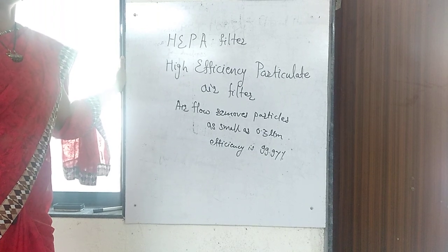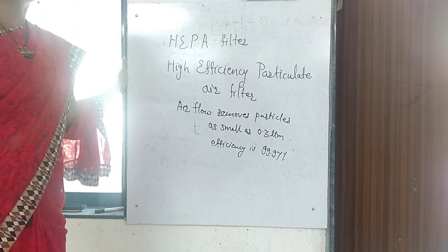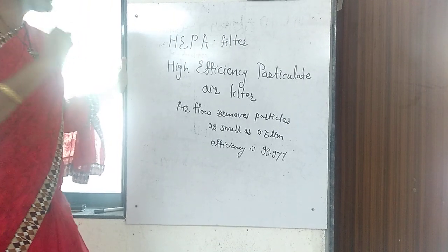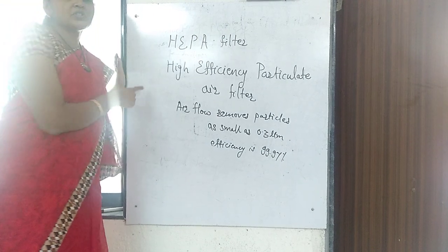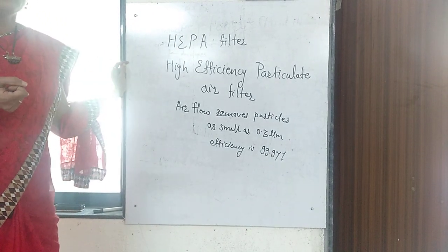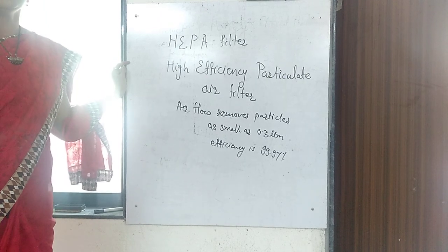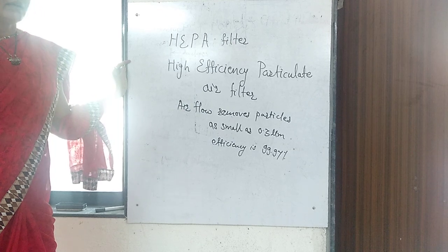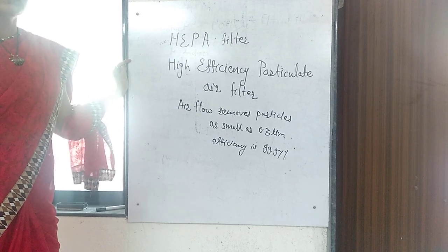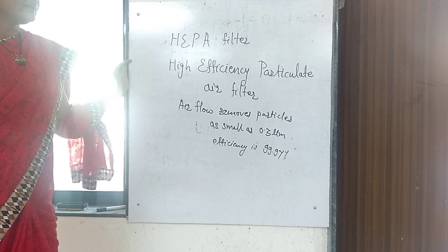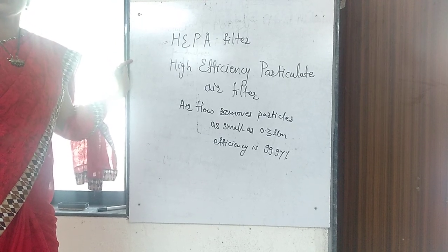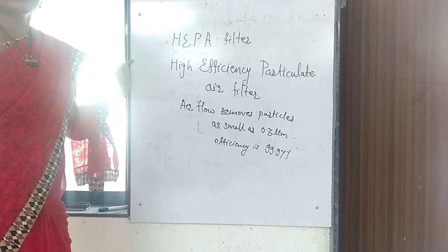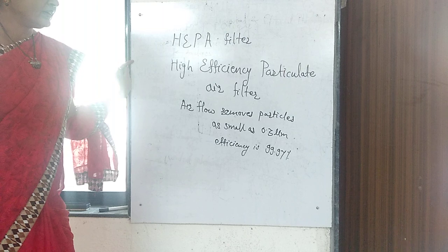So sterile air inside the parenteral preparation manufacturing area is achieved by using high efficiency particulate air filter. In the walls, horizontally and vertically, they are fitted, and the air present is continuously circulating and removes the particles that are less than 0.3 microns. They get deposited on the filter.